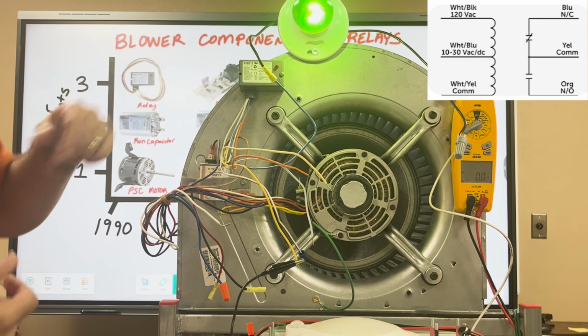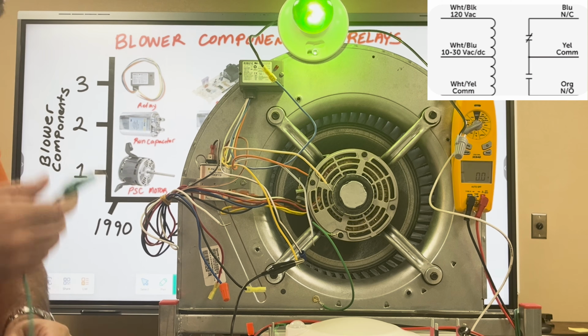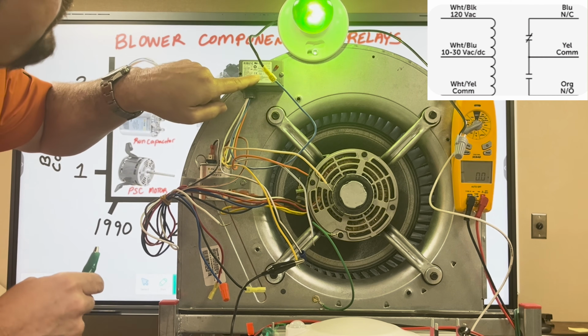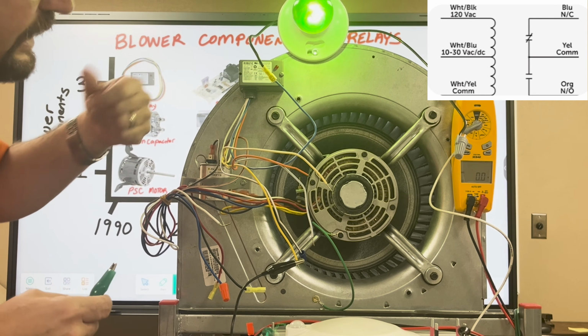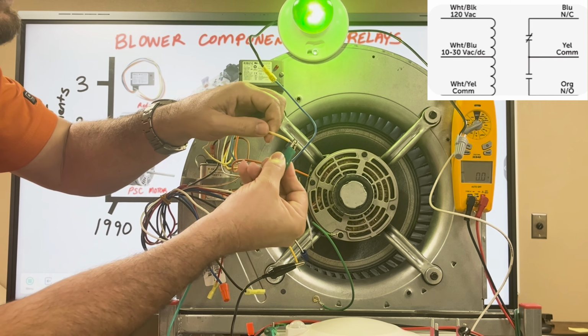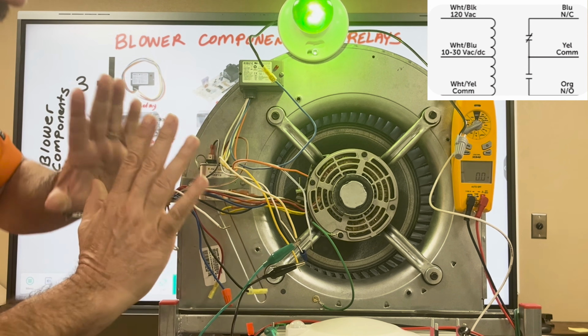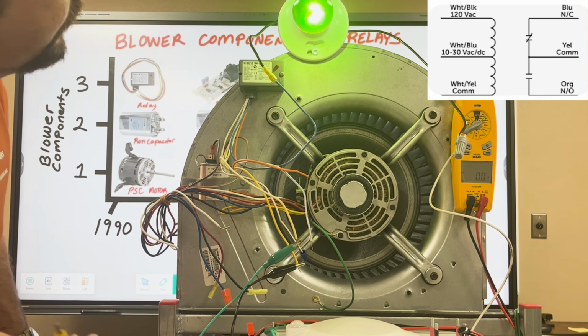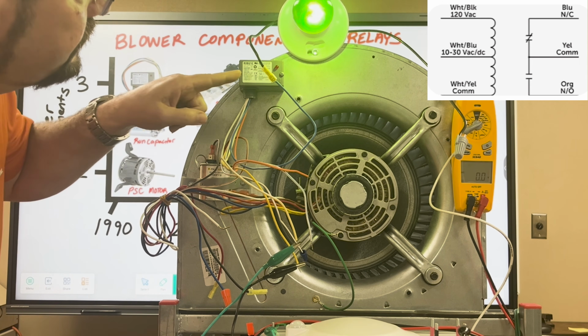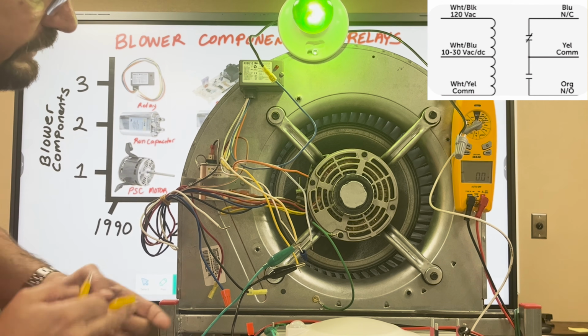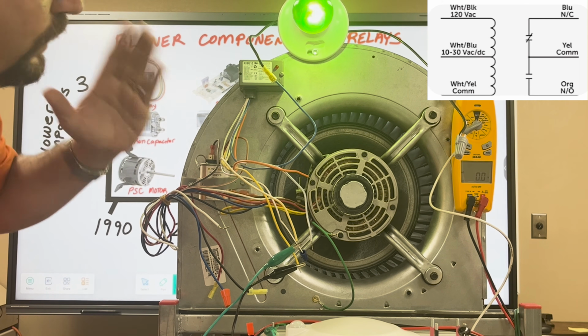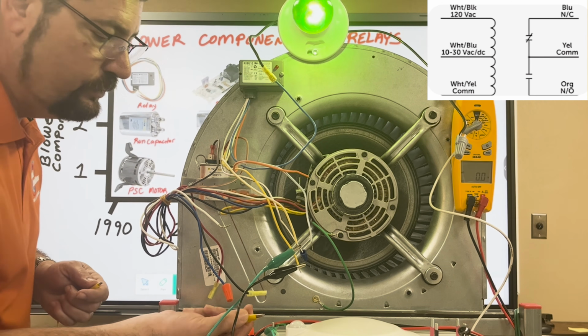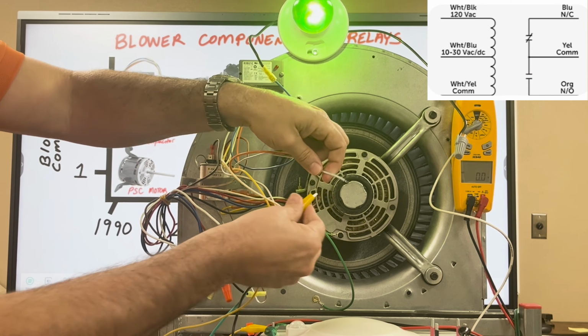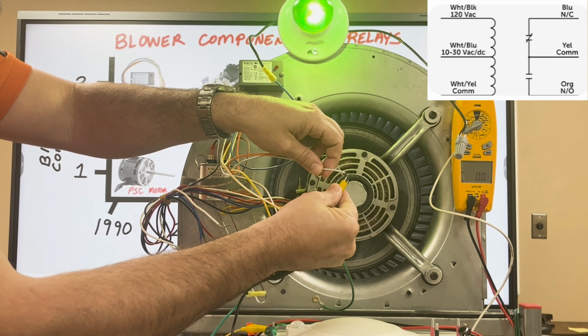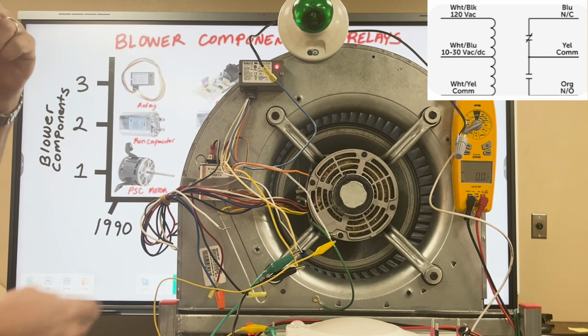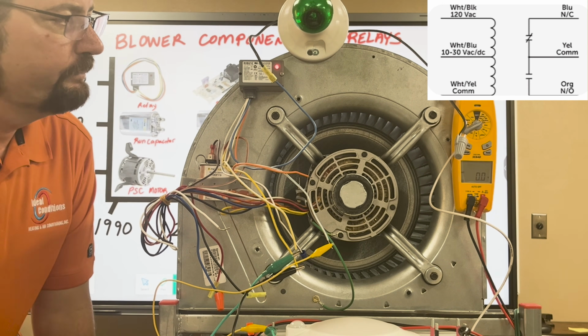Obviously the red light's not on here, so there's no coil voltage. I'm going to apply coil voltage now between common, and we're going to find common on the coil side, which are all my striped wires. So I'm looking for the white and yellow stripe. Here's white and yellow. I'm going to connect common to that. These are all floating, so I have to be careful not to touch anything or cross paths. And then we're wanting to use 10 to 30 VAC/DC because we're dealing with a 24 volt alternating current power supply. That'll be white/blue. So I'm looking for white/blue to energize the relay, which will open the normally closed side of the contacts. As you see there, the red light comes on, indicating that I have 24 volts on our relay.